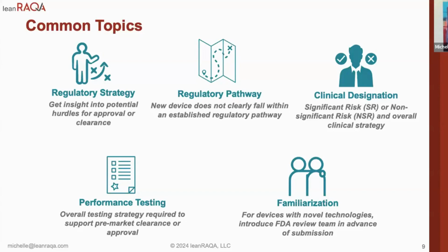And then also to ask specific questions about your planned performance testing, both the plan and then in the future, the protocols. And then again, this is a way for FDA to get familiar with your technology. So just that background in your technology will help FDA advance your submission more efficiently through the agency.